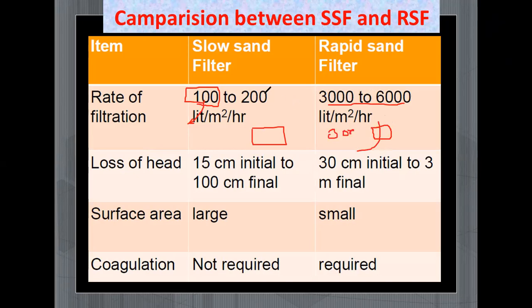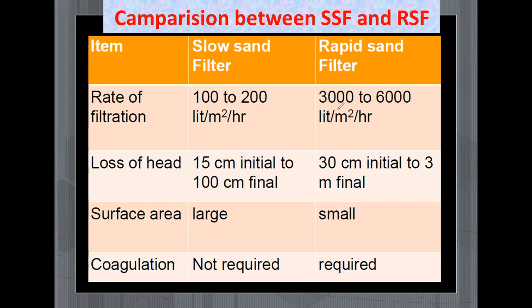This is a huge difference in the rate of filtration. Where there is a large requirement of water, if the size of the city is bigger and consumption of water is very high, in that case we should definitely prefer the rapid sand filter. Then comes loss of head — the loss of head in the rapid sand filter is more compared to the slow sand filter, because the rate of flow is very high. In the slow sand filter it is 15 cm up to 1 meter, and in the rapid sand filter it is 30 cm up to 3 meters.